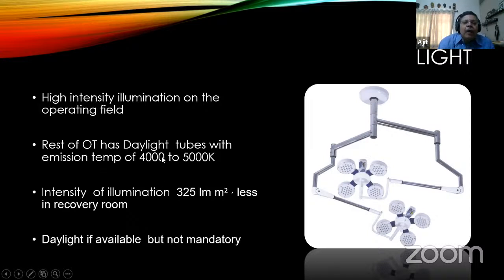The rest of the OT has daylight tubes with an emission temperature of 4000 to 5000 K and illumination of 325 lumens per square meter. The recovery room should be slightly darker for the patient's comfort. Daylight should be present in the operation theatre if available, but it's not mandatory.